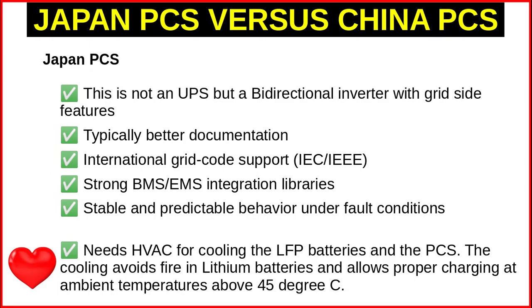I should point out here that because the PCS does not have an automatic current limiting feature as a function of temperature, an external EMS is required, which will do the job by communicating simultaneously to both the PCS as well as the BMS. Okay, next point, stable and predictable behavior under fault conditions.